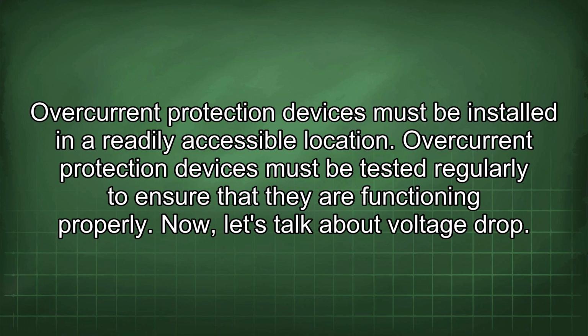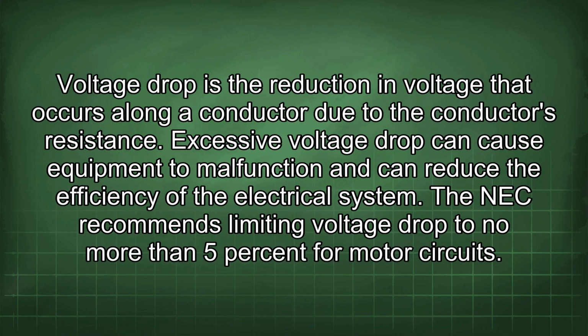Overcurrent protection devices must be tested regularly to ensure that they are functioning properly. Now let's talk about voltage drop. Voltage drop is the reduction in voltage that occurs along a conductor due to the conductor's resistance. Excessive voltage drop can cause equipment to malfunction and can reduce the efficiency of the electrical system. The NEC recommends limiting voltage drop to no more than 5% for motor circuits.